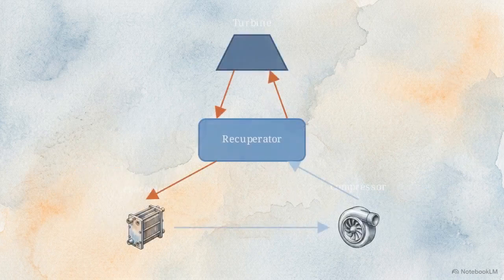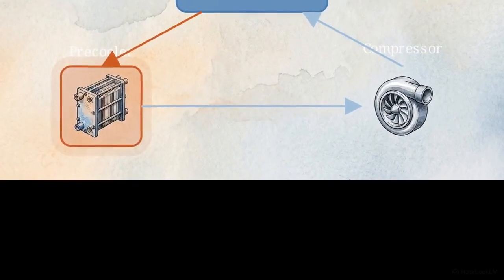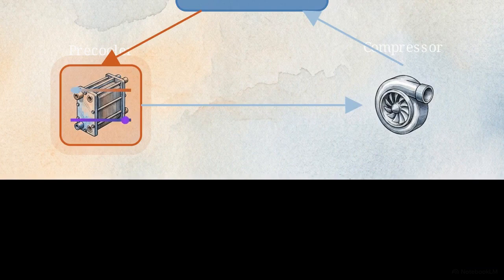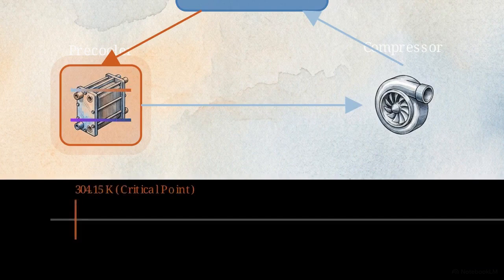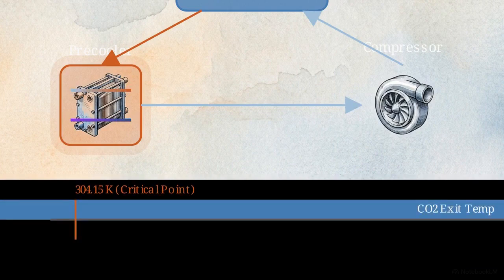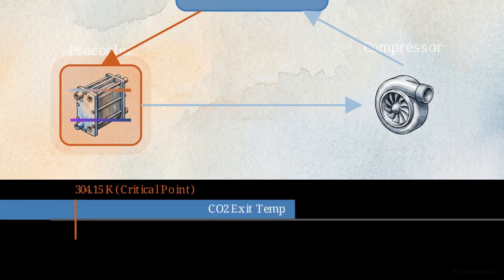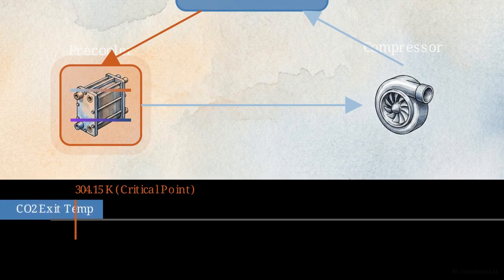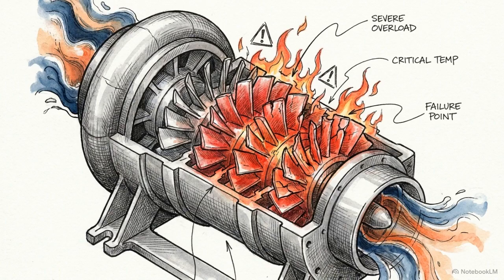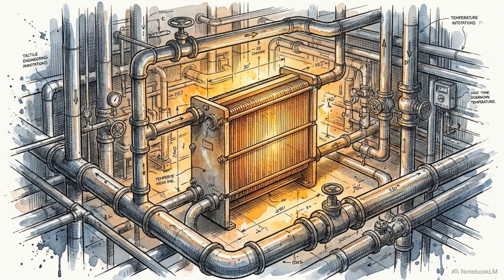But capturing that efficiency relies entirely on one specific operational bottleneck: the precooler. The precooler has a strict mandate. It must prepare the CO2 for the main compressor by dropping the fluid's exit temperature down to 304.15 Kelvin, a number remarkably close to its critical point. If the precooler fails to hit that precise temperature, the compressor takes on too much load.